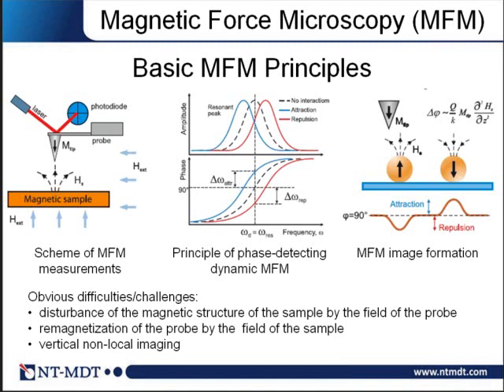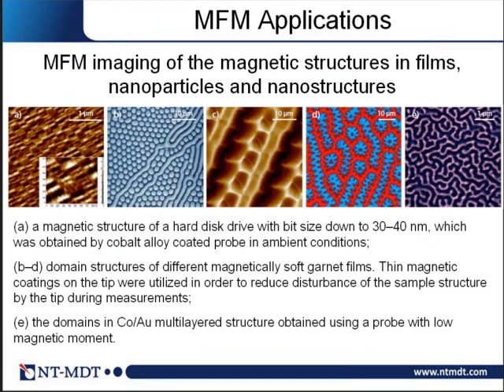When making a magnetic force microscopy measurement, you should adjust several parameters. For example, you can change the thickness of the magnetic cover layer — it might be a high magnetic moment material or a low magnetic moment material. You can also change the distance between the cantilever and the sample. By decreasing the distance you increase the interaction and signal-to-noise ratio; by increasing the distance you decrease disturbance of the probe on the sample and vice versa. Here we will see several examples of magnetic force microscopy applications.